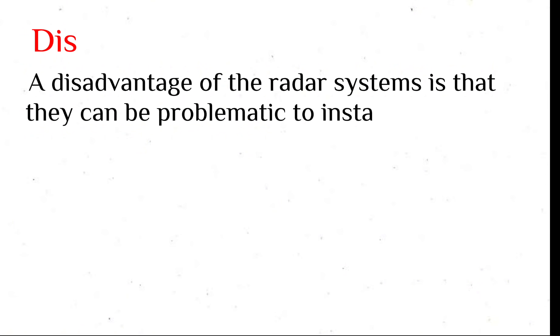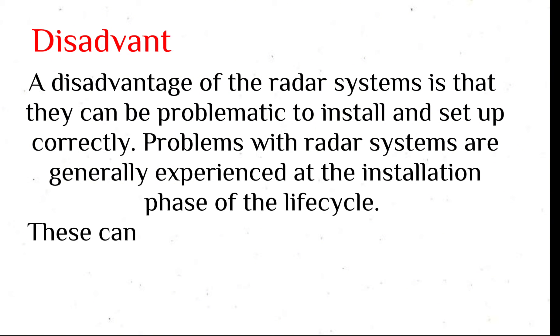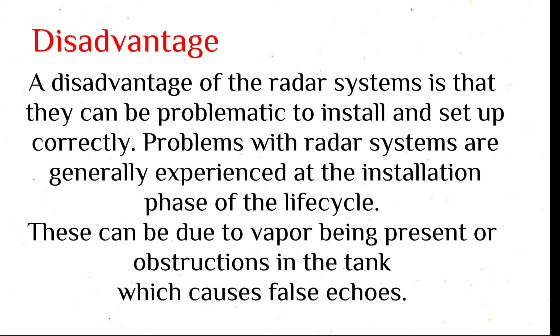A disadvantage of the radar systems is that they can be problematic to install and set up correctly. Problems with radar systems are generally experienced at the installation phase of the life cycle. These can be due to vapor being present or obstructions in the tank which causes false echoes.